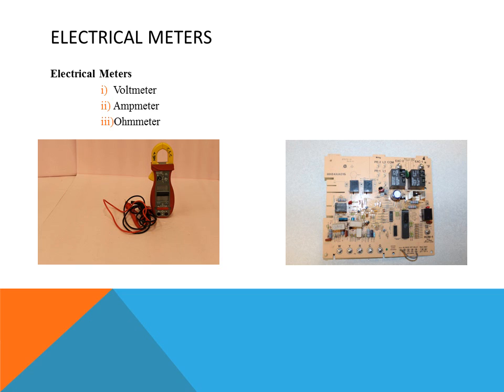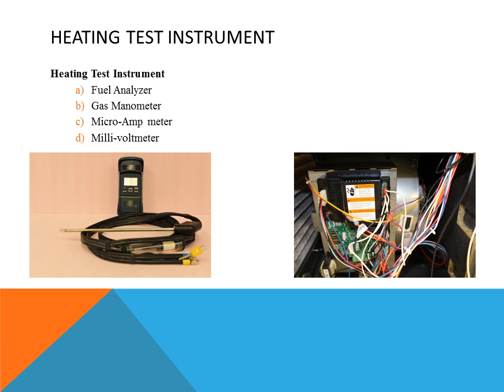When checking electrical systems such as the electrical board on a furnace, we need to check the voltage, amperage, or resistance of certain components to find out if the system is working correctly. When dealing with heating systems, we use specialized equipment designed to analyze the operation of the burners. For example, a gas furnace uses a fuel analyzer to record the flue gases and determine the percentage of carbon dioxide, carbon monoxides, or nitrogen oxides, to determine how efficiently the burner is operating.